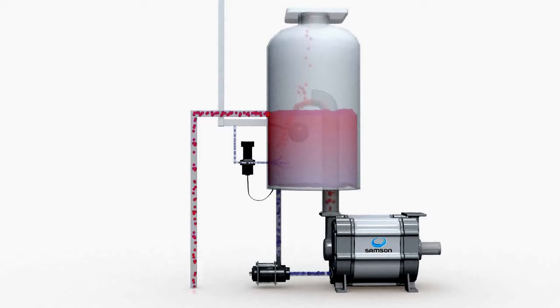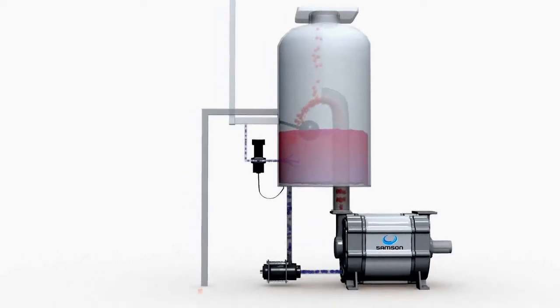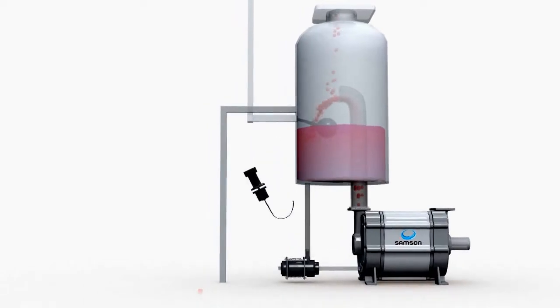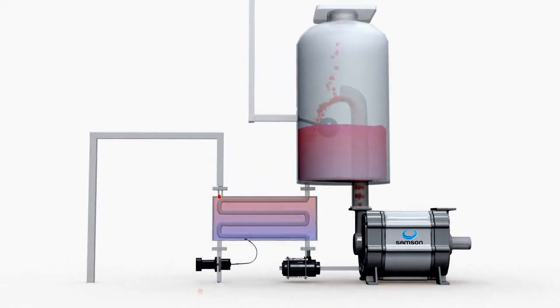Typically, the amount of water added is between 10 and 20% of the total water flow. In instances where access to external cooling water is available, water consumption can be reduced to a few liters per hour. The operating liquid for the pump is fed through a heat exchanger, where it's cooled before being fed back into the pump. The temperature regulating valve continues to ensure the correct flow of cooling water for the required temperature.